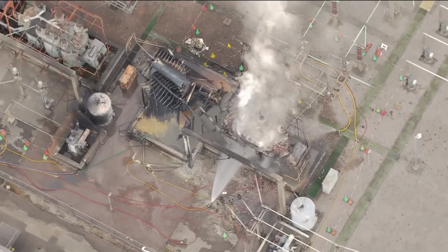When they identified the moisture levels, which they did, and it's great those were identified as part of regular testing, what got missed then was the action to take that transformer out of service and replace it. And they didn't pick up in later cycles that these high moisture readings were not acted upon at that point in time.